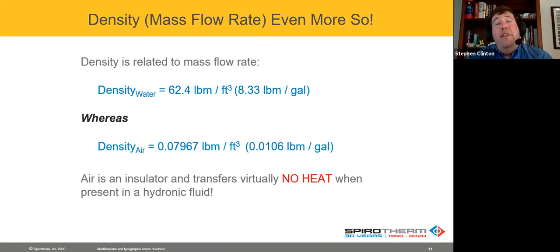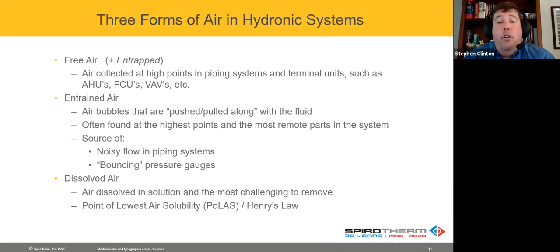If you had 5% of air in your fluid, that rule of thumb, 500 times GPM times delta T, is roughly 475, 10% and so on. It's a big deal. Now, if you have heard about the 3 forms of air, then okay, you probably will nod your head and go, okay, I remember that. Some of us who may not be familiar with it, this may be something new for you. There are 3 types of air you run into in a system. Free air: when you fill the system up, it starts off dry. You have to push the air out of the way to make room for the water. That's what high point air vents are for. They allow you to push the air out to make room for the water.